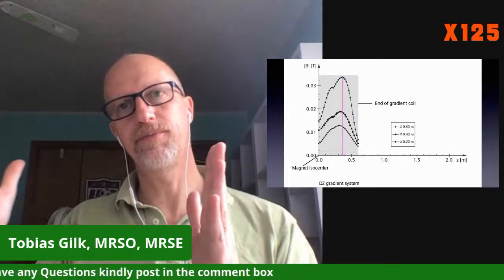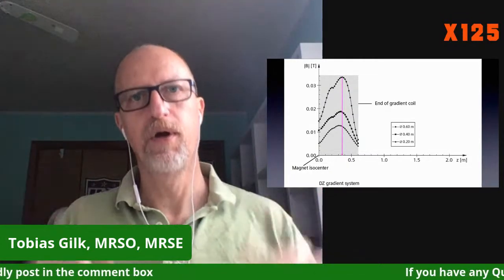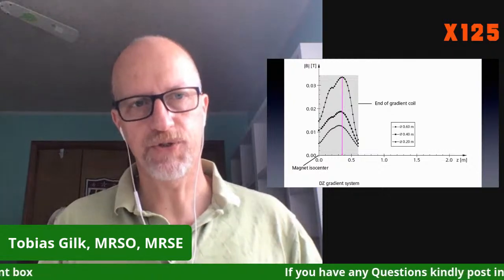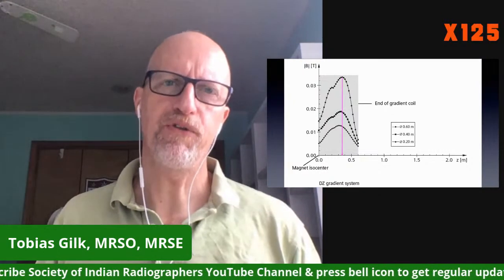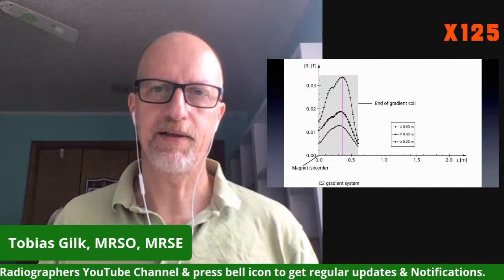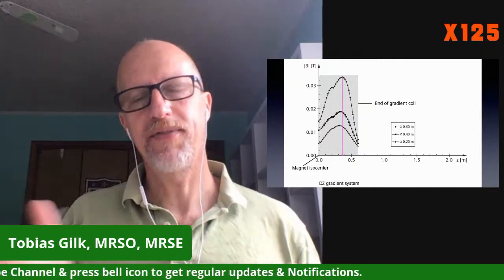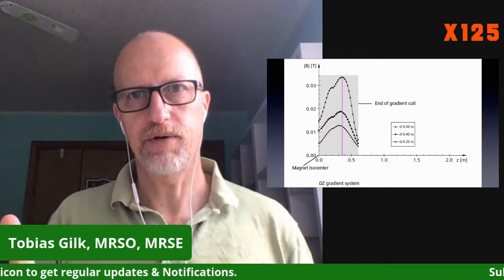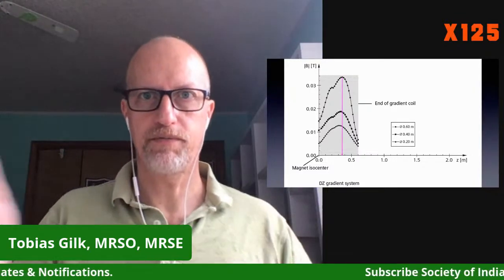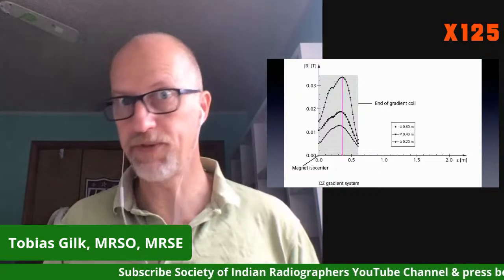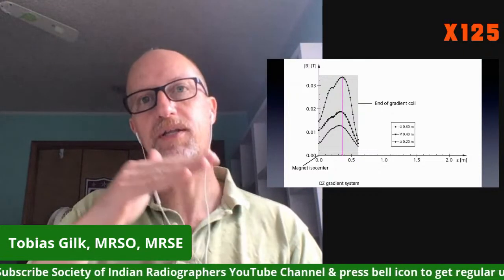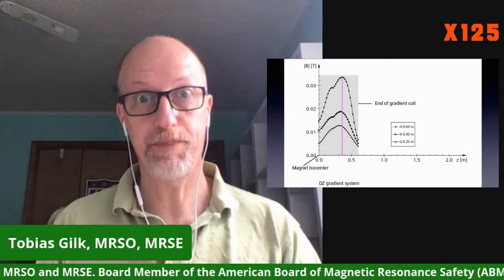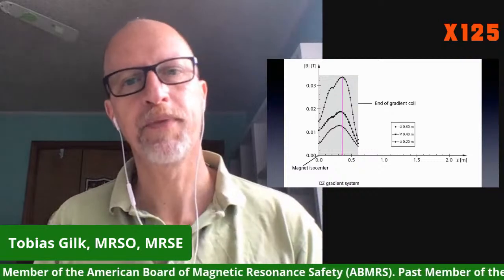As you move both inferior and superior from isocenter, and you move radially, this is where you will experience the greatest time-varying gradient amplitude. Once you get beyond that 30, 35 centimeter superior-inferior distance, now you're 40, 50, 60 centimeters superior or inferior, you can see that the time-varying gradient energy, the amplitude, drops off precipitously after that.